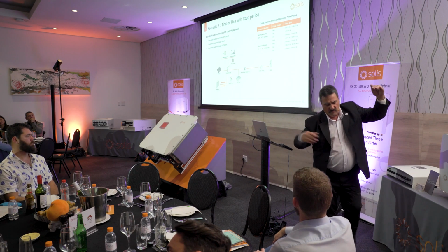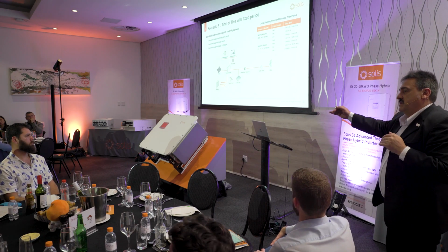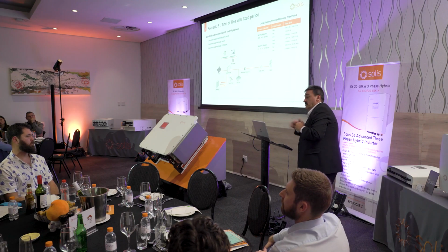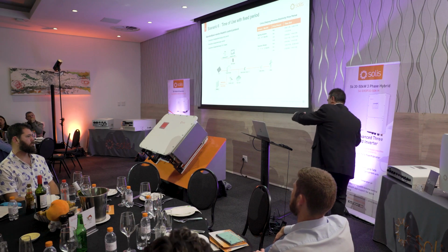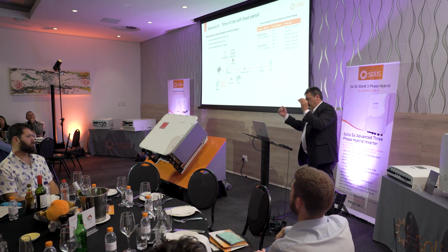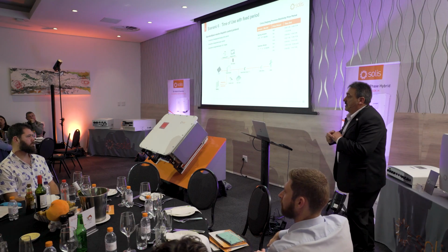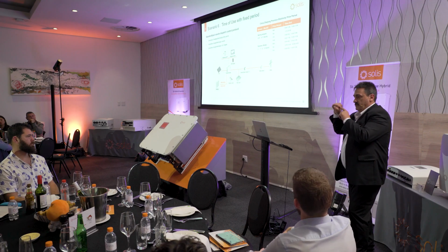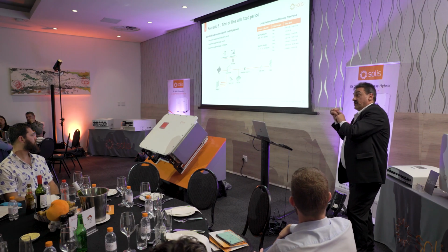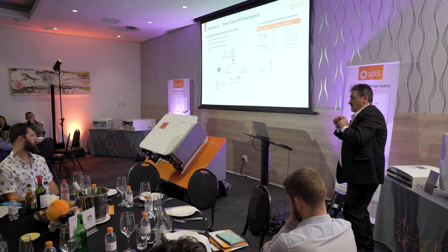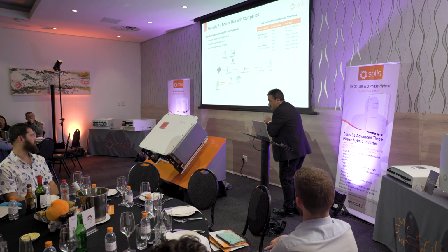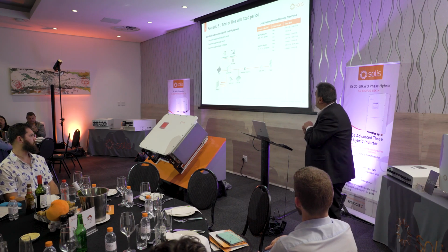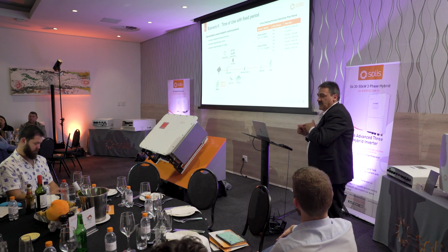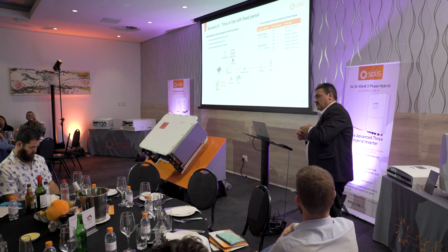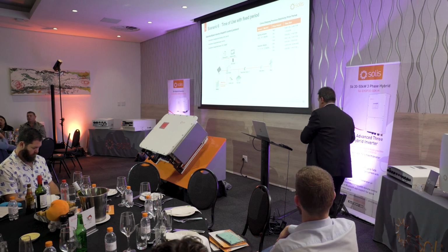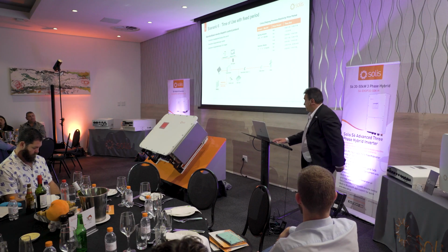But let's say your battery is at 100% when it starts. You can then set the SOC against that time. So let's say you set that at 90%. Say for whatever reason you are using more energy, it's not going to last you through your 2 hours, but you're going to hit the 90% after 1 hour. Remember, 90% is your control point, you being the boss there. So you can use all of that till you get to 90%. After that, you can stop, no more discharging. And you can set that for every time slot, whether you're charging or discharging. There's an SOC associated setting for that, so you have 12 of those through a 24-hour period. So you've got a lot of flexibility. You can even set the discharge slot for when the kids come home in the afternoon, at night when the house gets busy. So you've got a lot of flexibility in the system for that.